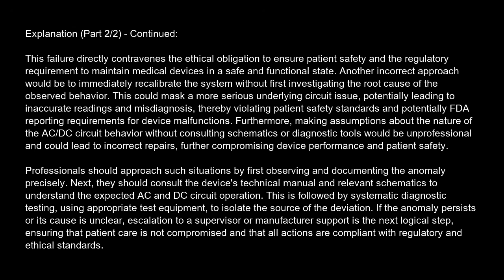Professionals should approach such situations by first observing and documenting the anomaly precisely. Next, they should consult the device's technical manual and relevant schematics to understand the expected AC and DC circuit operation. This is followed by systematic diagnostic testing, using appropriate test equipment to isolate the source of the deviation. If the anomaly persists or its cause is unclear, escalation to a supervisor or manufacturer support is the next logical step, ensuring that patient care is not compromised and that all actions are compliant with regulatory and ethical standards.